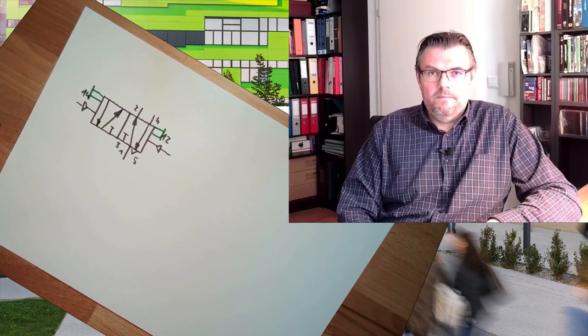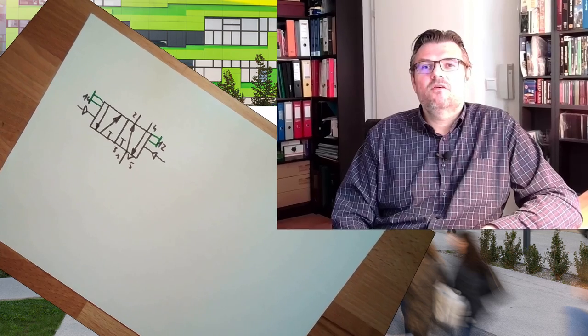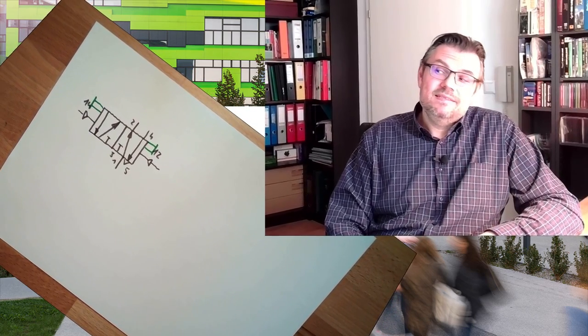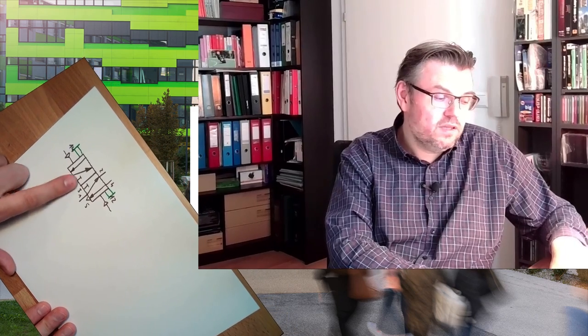Sliding valve. Next time, we're again talking about a pretty similar approach. By the way, this was an impulse valve. This means if I release the pressure on 1-2, this will stay in the position where it is switched. I don't have to put on pressure all the time to 1-2 or 1-4. It will stay there. Impulse controllable. If there is only a pressure peak, a pressure impulse, it will switch and then stays there. Impulse valve. I just wanted to tell you, but luckily next time we're also talking about the impulse valve. So I remembered.